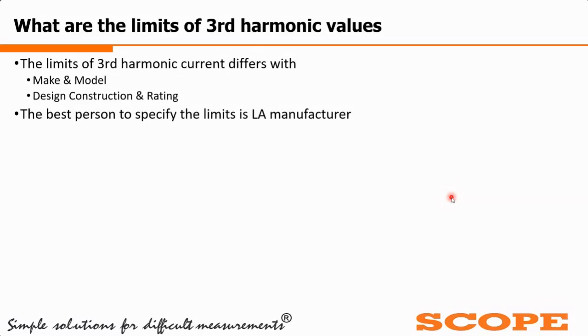It must be mentioned, and your factor must be mentioned, and what should be the value at which it should be taken out. Like you know about breaker timing, the safe operating zone, the operating time of the breaker, what the closing time of the breaker should be, what the tripping time of the breaker should be. That is not told by the instrument manufacturers who make the kits measuring the timing of the breaker. Those manufacturers are not giving those values. You ask those values from the breaker manufacturer. Similarly, over here, it's better to ask the LA manufacturer for those values.